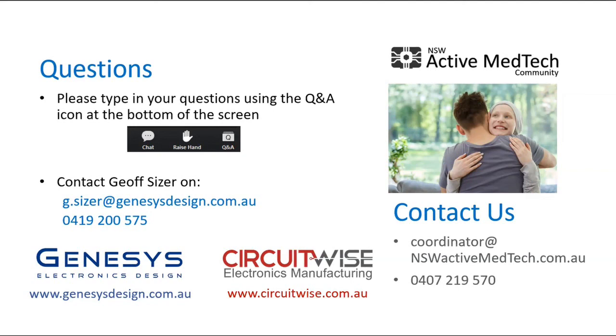I've got another question here, which is how do you keep track of all the documents? The process that we use here is to set up at the start of the process what we call a hierarchy diagram, but it's essentially a structured representation of the items in the medical device, all of its component parts and sub-assemblies and printed circuit assemblies, etc. And we identify all the documents that are required as a part of the design control process to be generated. And we have that in a templated form, and we use that to actually create that list at the very start of the project. You might say, well, how can I possibly know what that needs to be when I haven't even started the development?